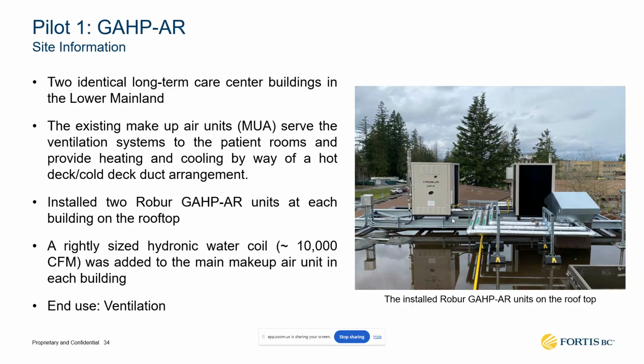It can also provide cooling. The main reason our customer wanted to install this unit is that this building currently has mechanical cooling that had been working fine for the last couple of decades, but since we started with the heat dome events in the last couple of years, they just didn't have enough cooling capacity, and they couldn't increase the electrical capacity at all. So what is going to happen is that during a normal year, the existing mechanical cooling will be running.